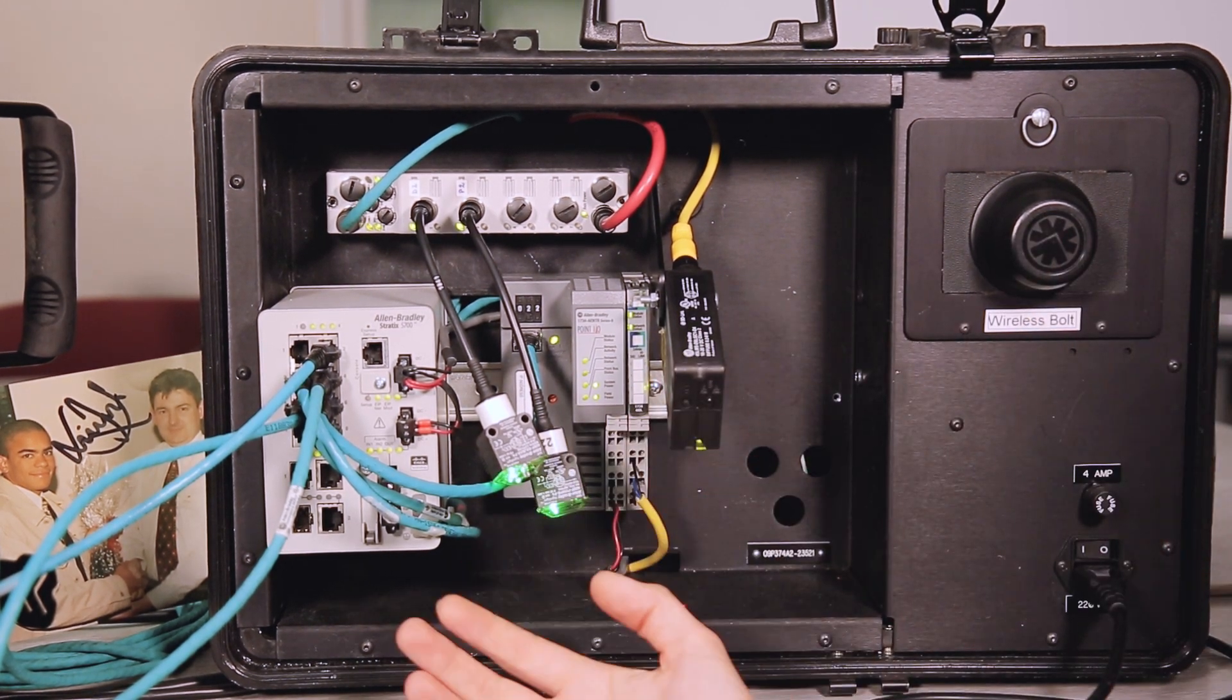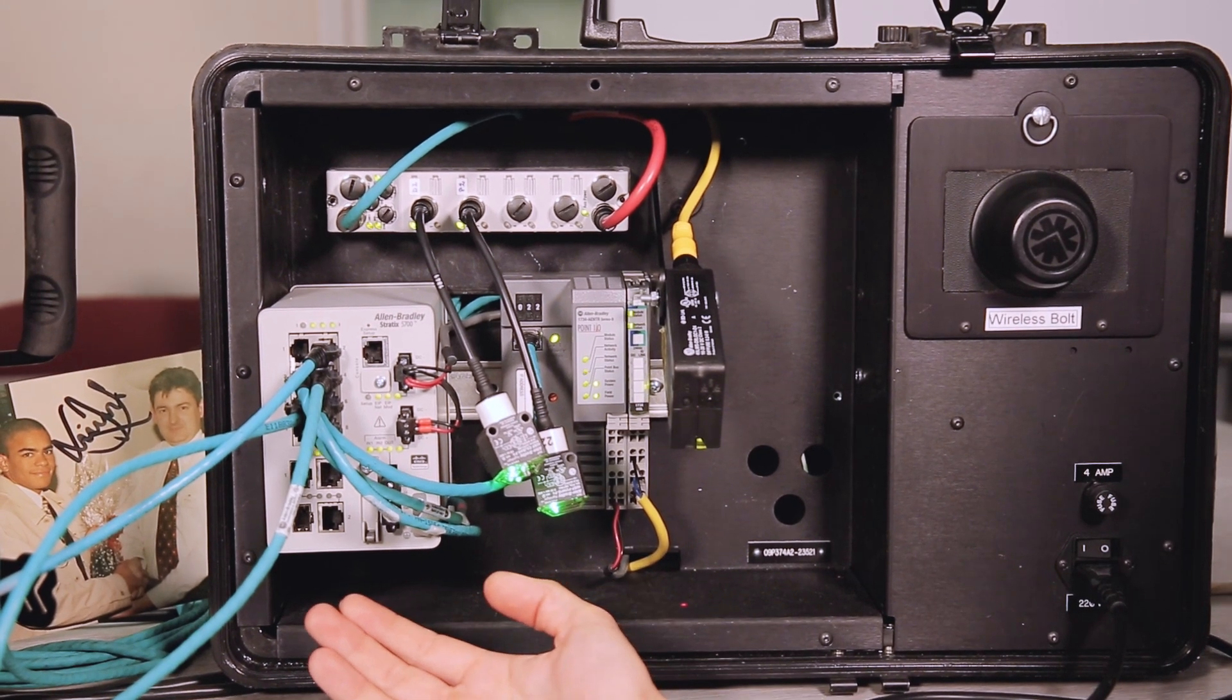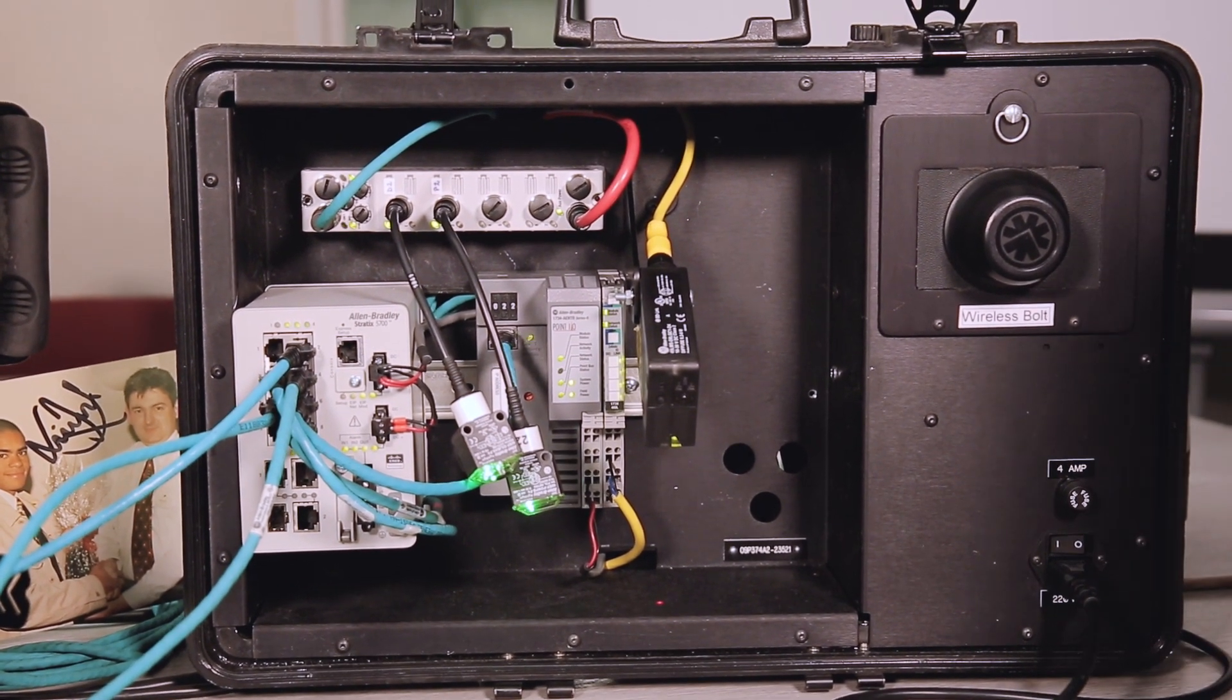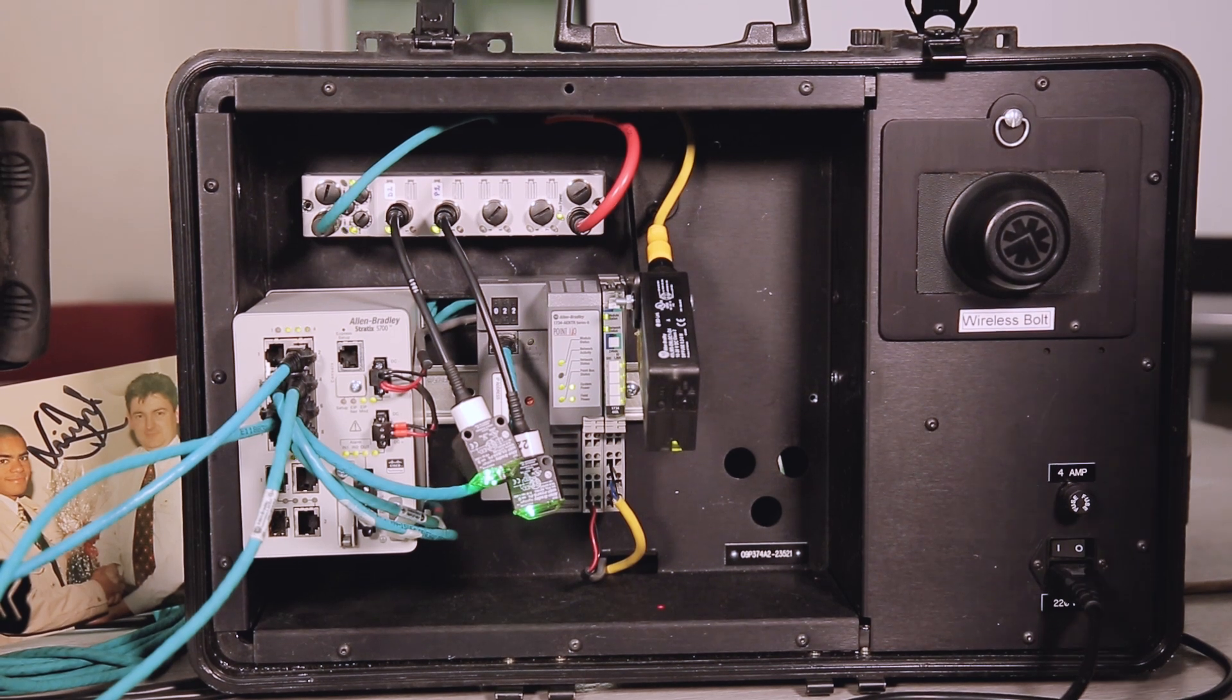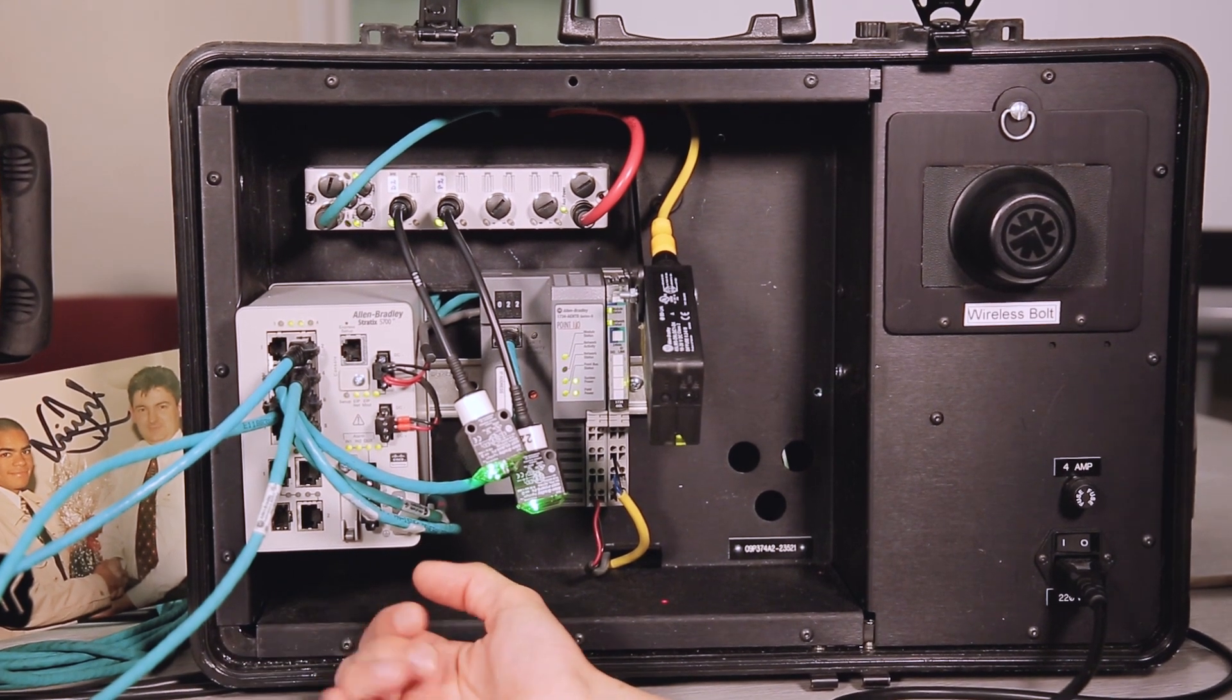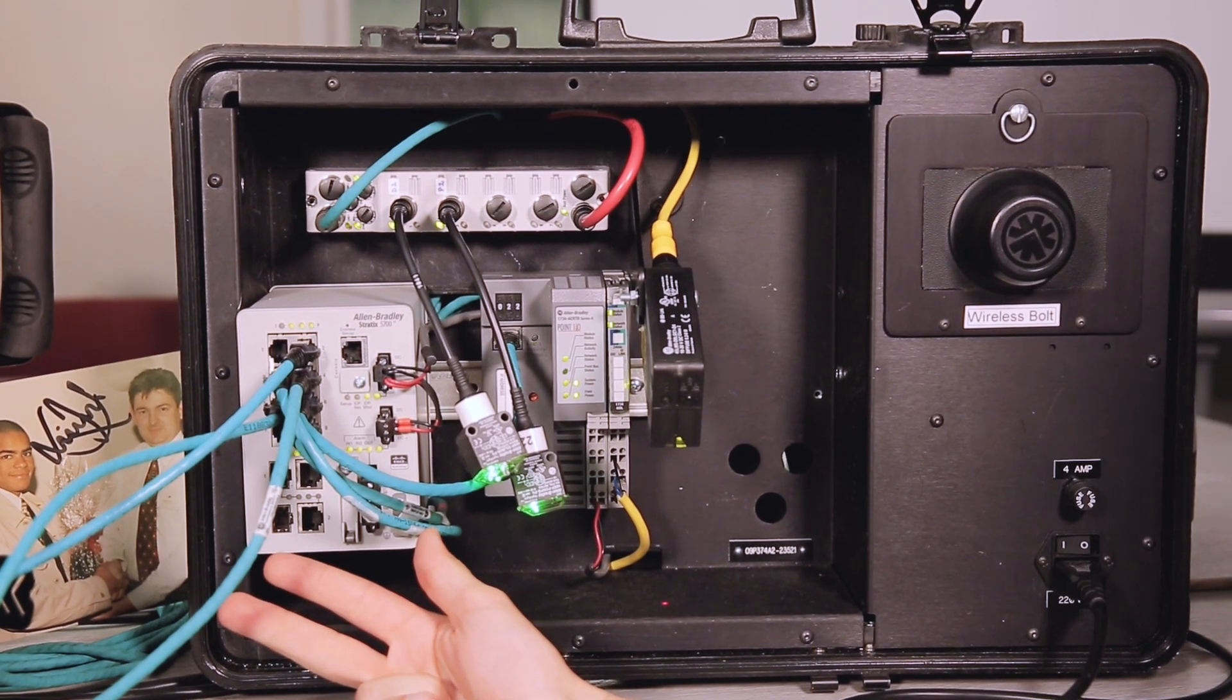This is mainly our sensor demonstration case with IO-Link, but I'll start from the bottom left which has got our Stratix 5700 managed switch. This is Cisco inside with Rockwell functionality designed to integrate into our PLCs and SCADA. We've got SFP fiber ports and what managed switch will allow you to do is prioritization of traffic, security, and provide quality of service.